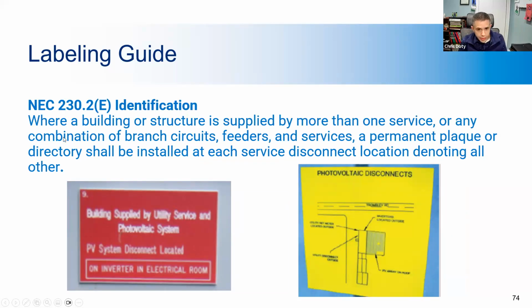So here we have, for a supply side connection, NEC 230.2 requires a directory of the location of each service disconnecting means, just like I just mentioned. It can be accomplished by either a simple description of the location, like in the photo on the left, or a map of the building as seen on the right, showing where the disconnects are.